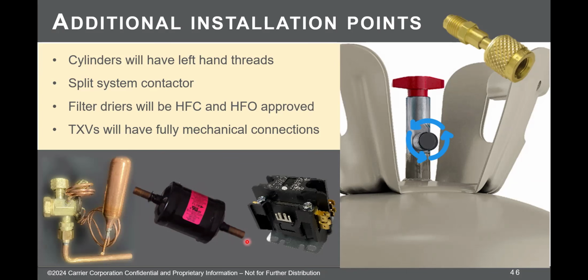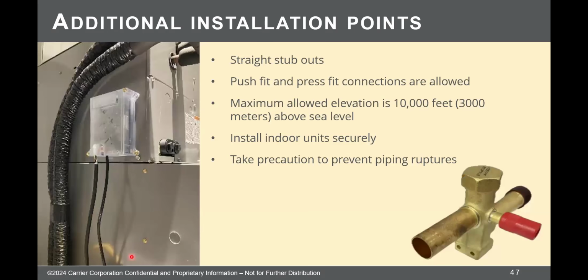So you can use one from inventory that's a regular filter dryer that's swedged on there. You can put that on 454B. Obviously, this one comes with the unit, but maybe they used it and they got plugged up and now they need a new one. You don't have to have this exact one. You can give them another version of it. In any case, it's straight stubs on the side. The coil has straight connection on it as well, and the outdoor units have straight connections on them, as opposed to being swedged. Swedged means it's like flared out a little bit, so you can stick the pipe inside there.